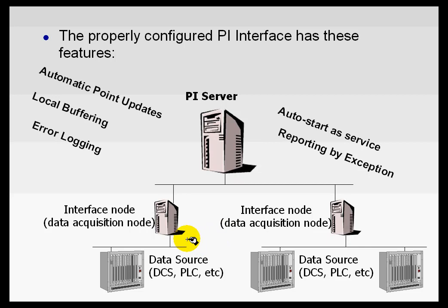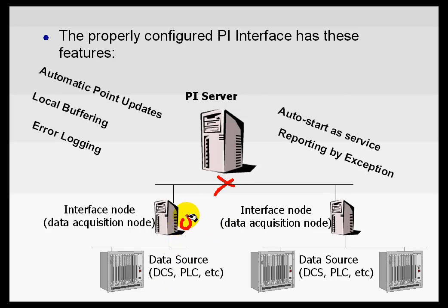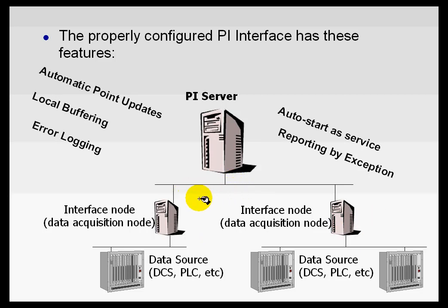What we're talking about is a data source in the field that we need to collect data from. The data is going toward the PI Server by means of an interface node, and running on that interface node is an application called the interface. If you were to disconnect it from the network, should the interface keep trying to connect to the data source? Yes, it should. Also, should it be able to buffer the data automatically if that connection should fail? Yes, we think it should buffer the data automatically.